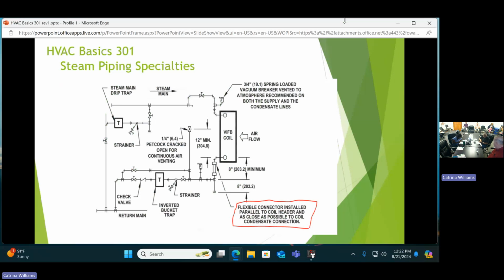How big are those traps? I mean, you can tell by this schematic. That trap will be, they're cast iron traps, and typically a bucket trap is about that big. So it's not huge. A pump trap, which is a different kind, actually has a receiver built into it, and it pumps the condensate out. They get quite large. Depending on the pressure and the temperature and how much condensate is going to be coming off of that coil, we calculate all that, and that'll tell you how big a trap.